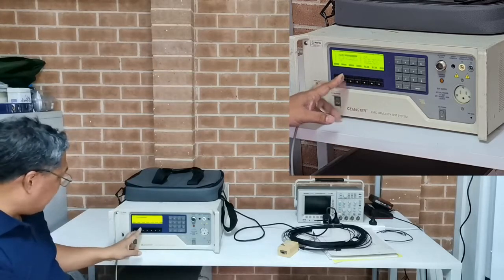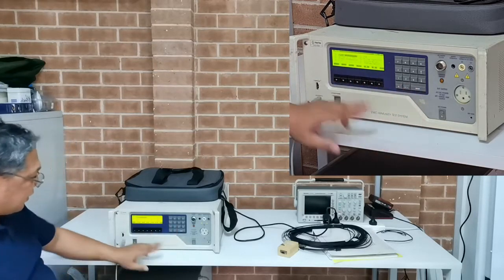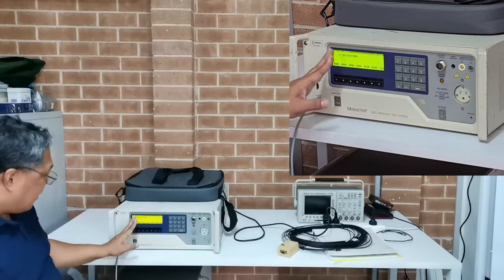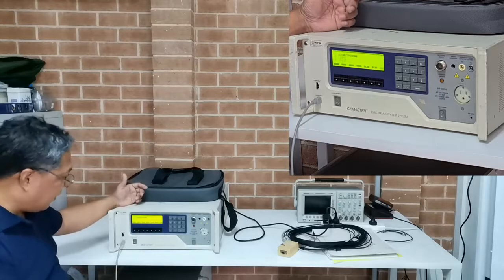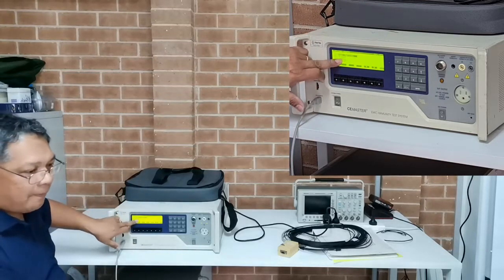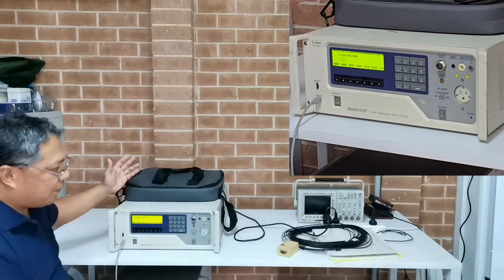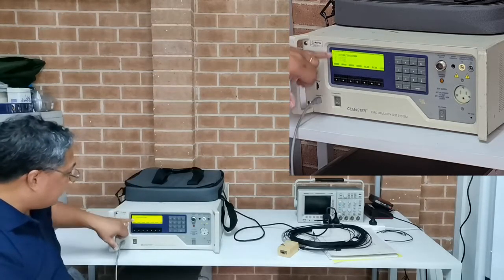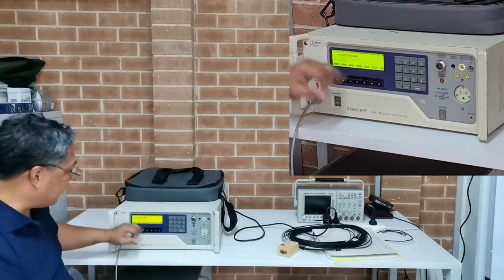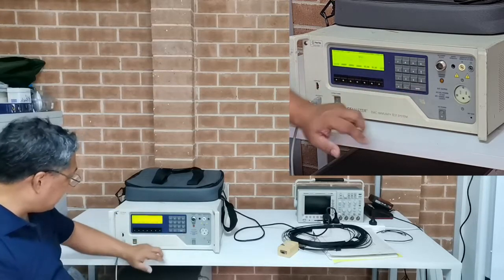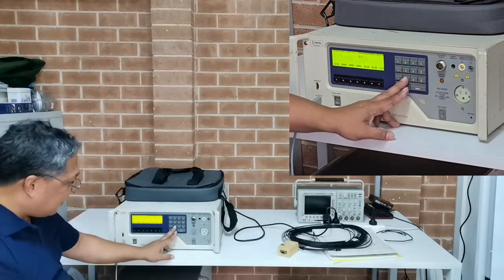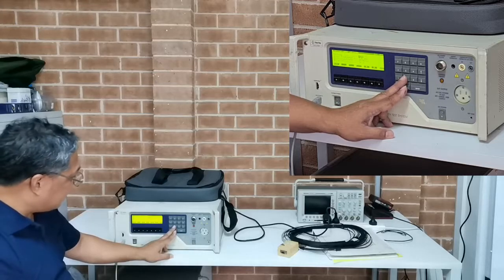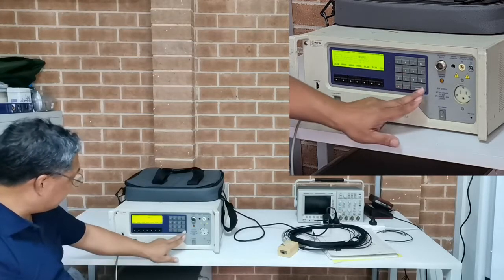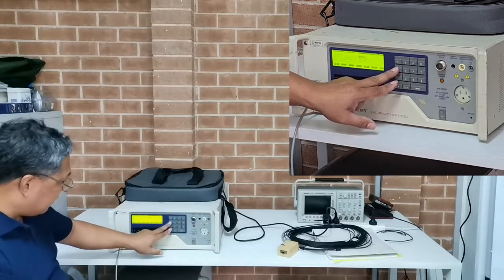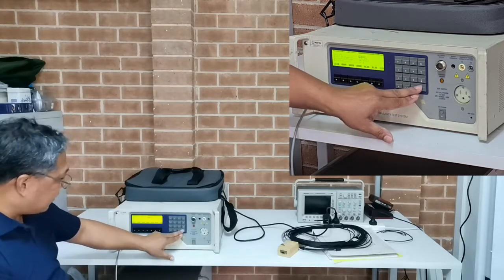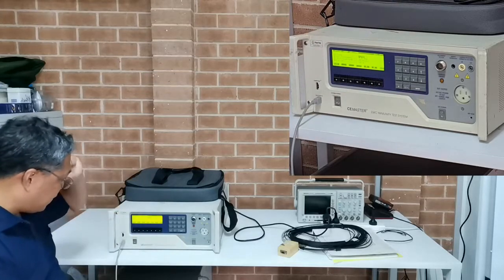So first we need to do the EFT. When you select EFT number 1 and press enter, you can see that the EFT option is working. Otherwise, we won't go into this option. If the EFT card is not plugged in or is not active, it will say that this option is not available. With user defined, I can set a voltage up to the maximum, which I know is 2000 volts only, but I will try 2500 volts. It works at 2500 volts. Let's go to 4000, and it should default to the maximum. So it's only 2500 volts for the EFT.